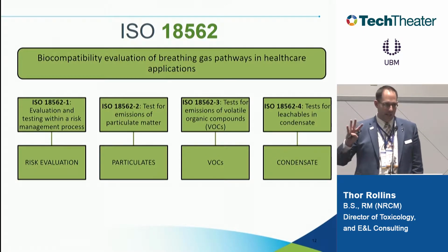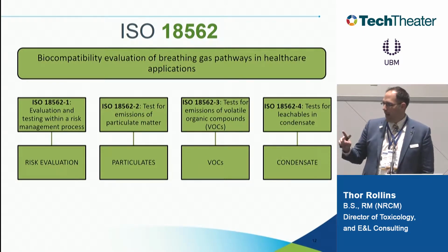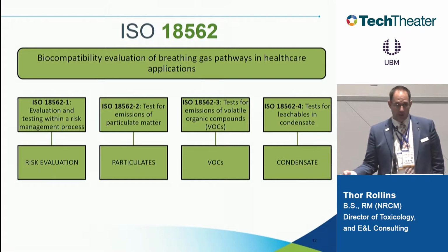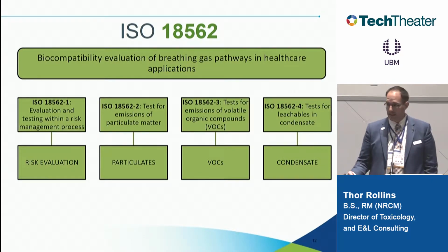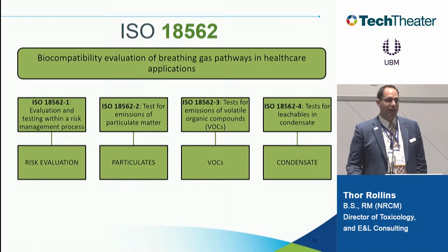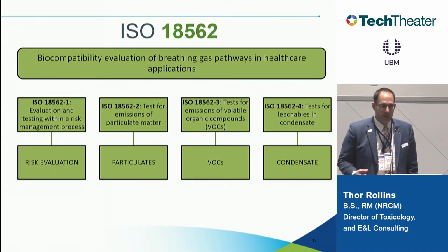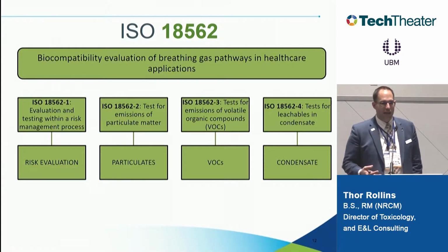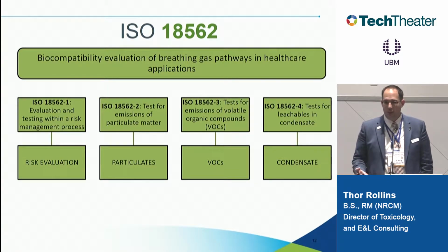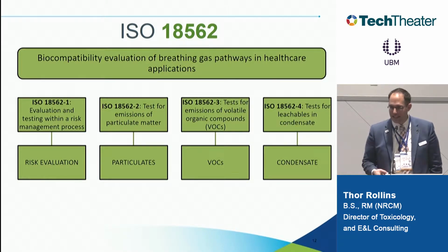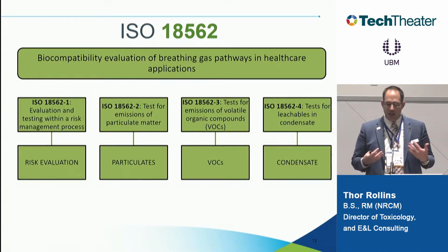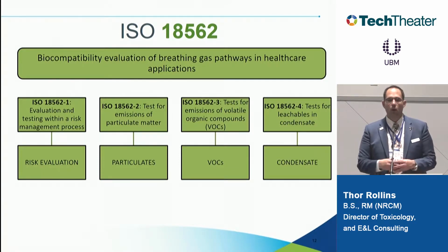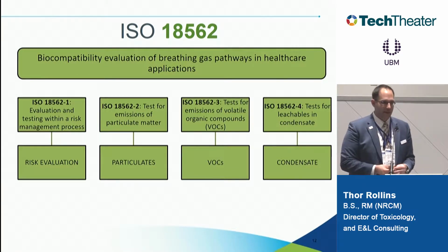There are 4 parts in the standard. The first part has to do with the initial risk evaluation, kind of like we talked about already, an important part of all medical device toxicity testing. The second part has to do with particulates. If you're thinking about the risk of a medical device, when you're thinking about gas path, particulates are a legitimate risk. When you're breathing in gases, if you're shedding particulates from a plastic, from an adhesive, or something like that that are being lodged into the lungs, that causes a legitimate biocompatibility concern. So we need to evaluate particulates for gas path devices.